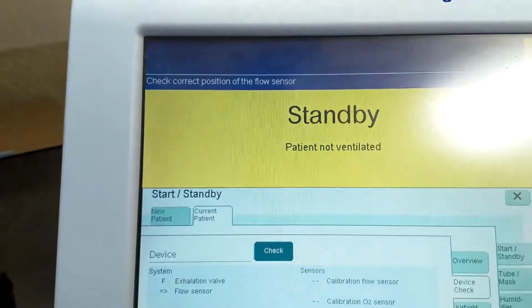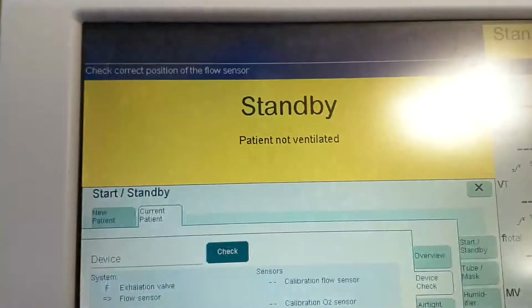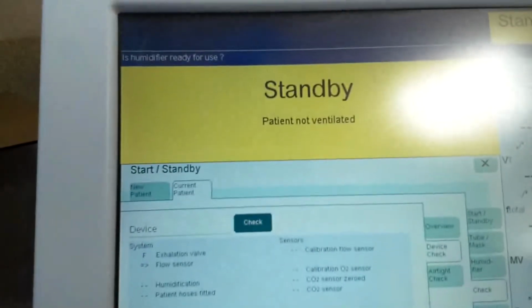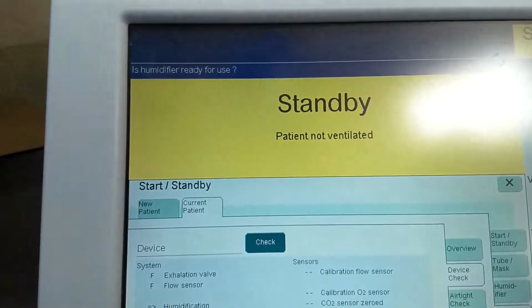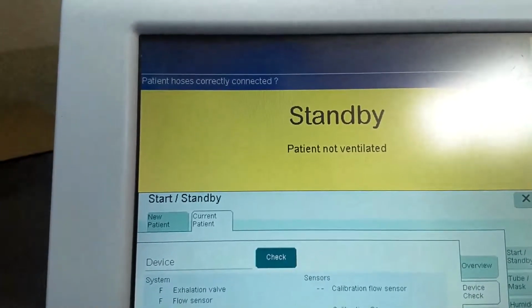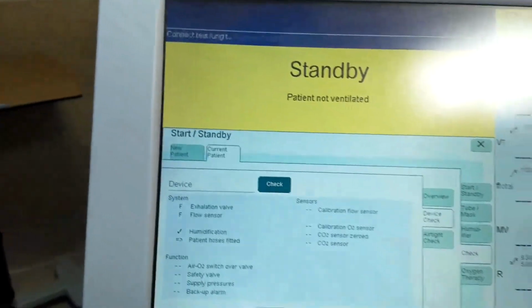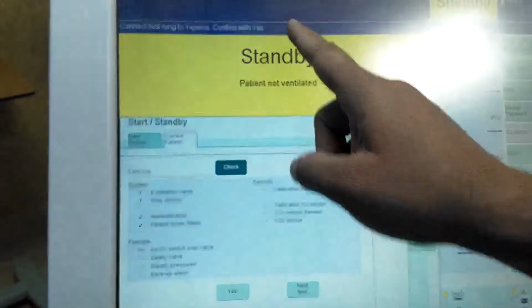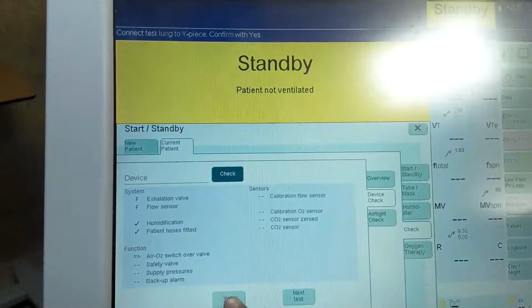Now let us wait. Check correct position of the flow sensor. We already checked the position of the flow sensor, so we'll give yes. Is humidifier ready to use? Yes. Patient hose is correctly connected. This is the patient hose. We have connected one to the inspiratory side and the other to the expiratory side. So the patient hose is connected properly, and we will give yes to that question also. Connect the test lung to the Y-piece. We already connected it, yes.